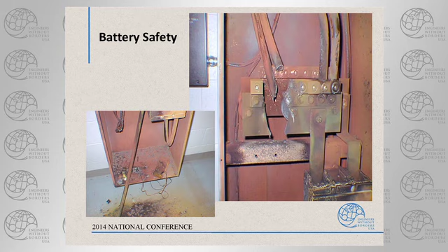So working with battery systems, realize the voltage may not be that high on a 12, 24, 48 volt system, but if a short, a fault occurs, you can get an incredible number of amps flowing. Battery won't shock you. You can reach across a 48 volt system, touch it barehanded, you won't feel anything, go about your business. But if you get it faulted with something conductive, you're going to vaporize metal. When that metal is vaporized, metal and human tissue are a poor mix. Don't try it. Bad. Notice a little Fluke meter down in the bottom of the breaker can there. So yeah, pay attention to what you're doing. Let's go to the next one.